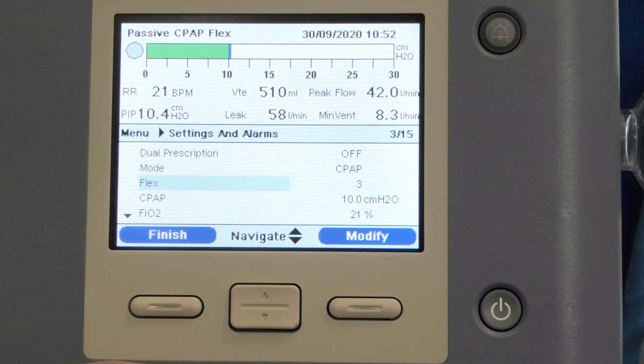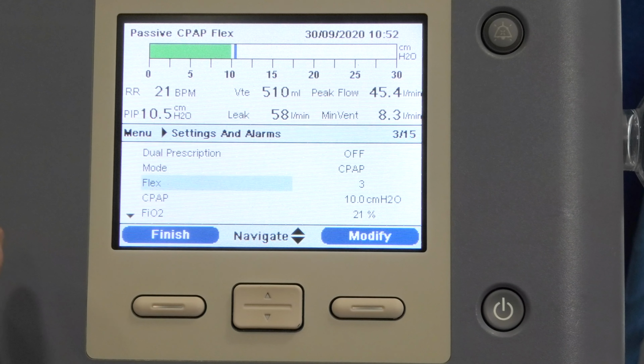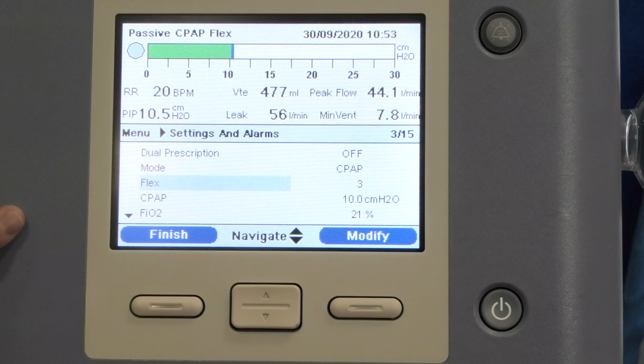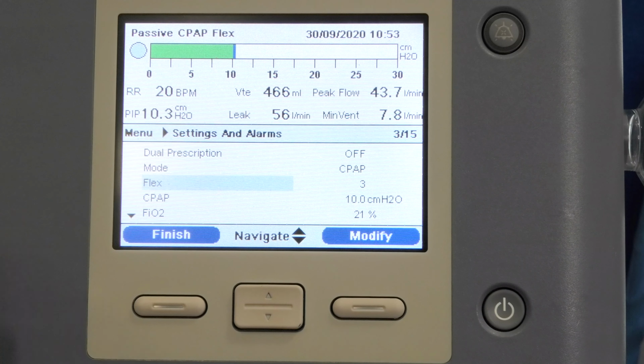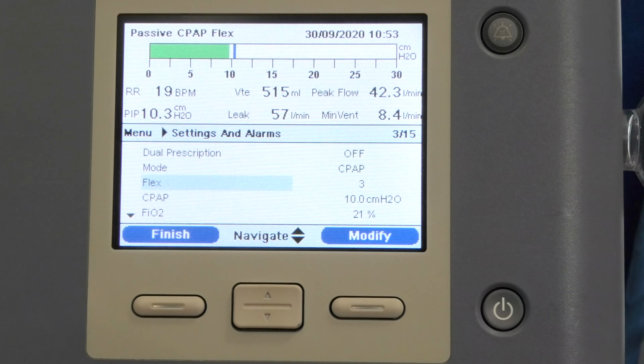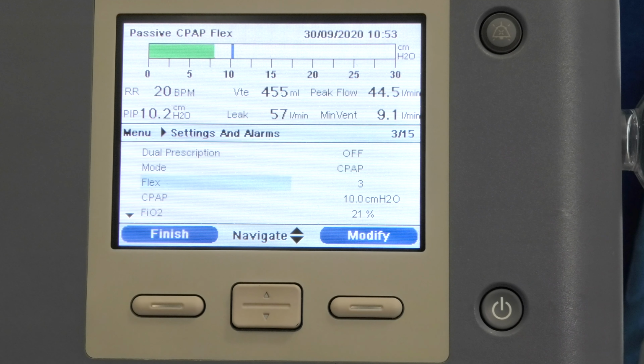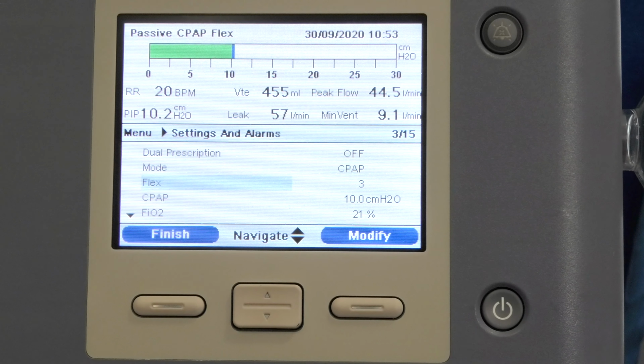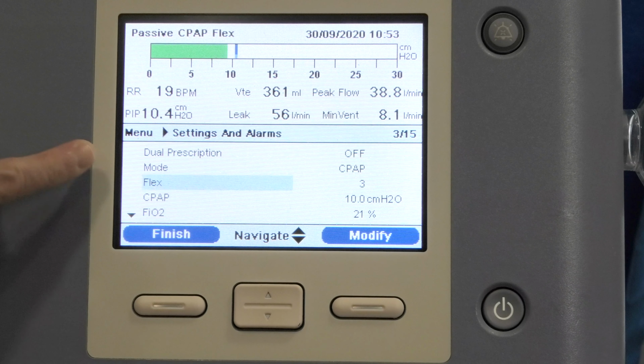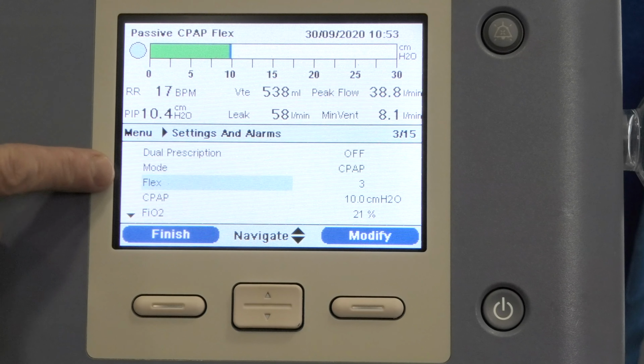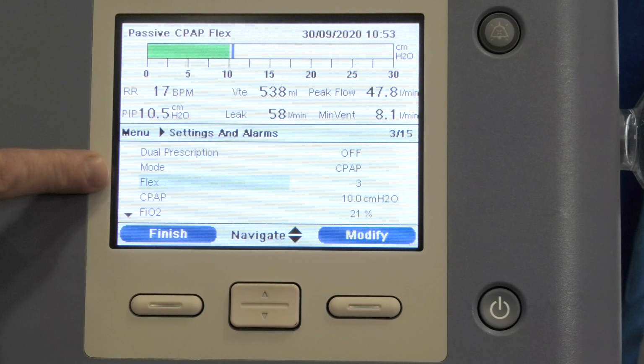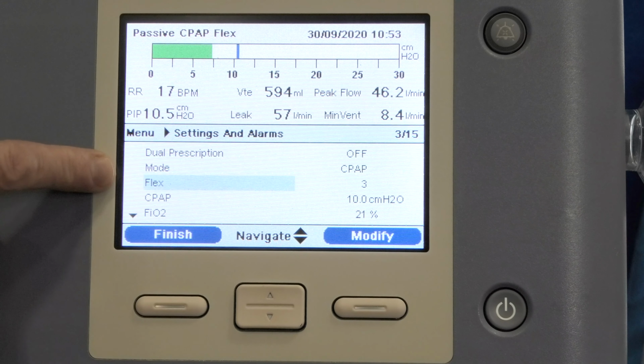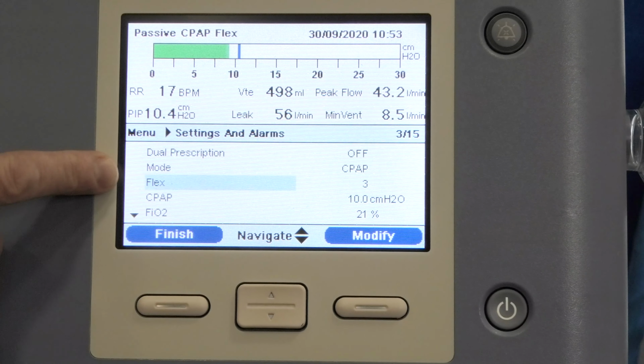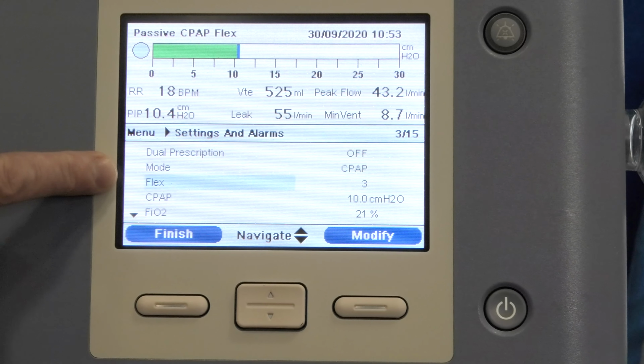So during inspiration, the ventilator blows at the patient to maintain a PEEP, in this case of 10 centimetres, or CPAP in this case of 10 centimetres of water. We find that patients find it very uncomfortable to breathe out against a pressure of 10 centimetres of water, and actually you get spikes of pressure within the mask at the start of exhalation. So what the flex does is it decreases your pressure within the mask by 3 centimetres of water at the start of exhalation, which makes it much more comfortable for the patient and improves compliance.